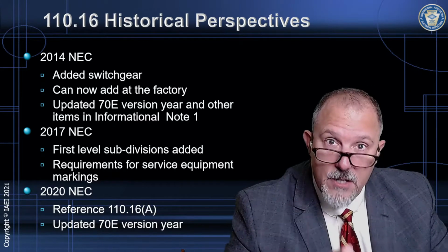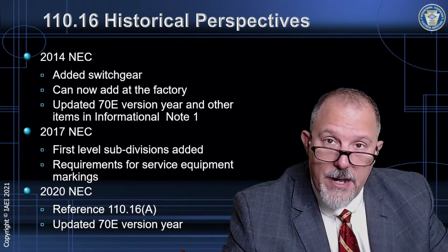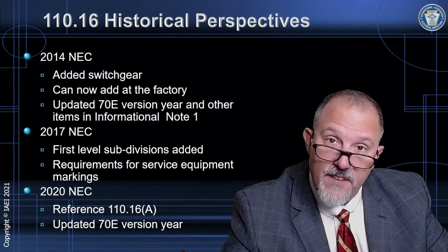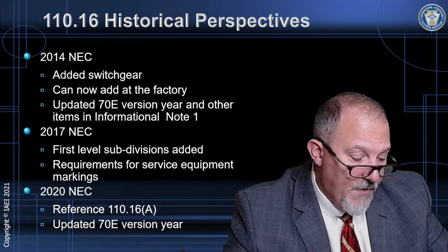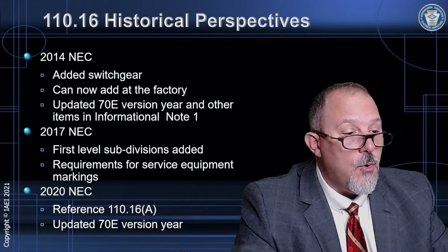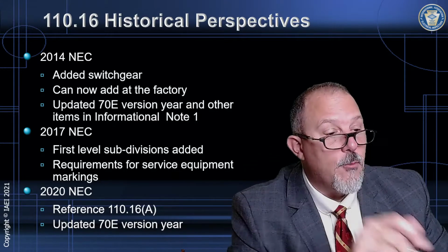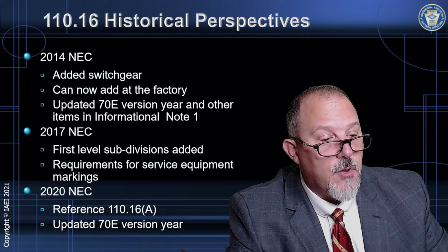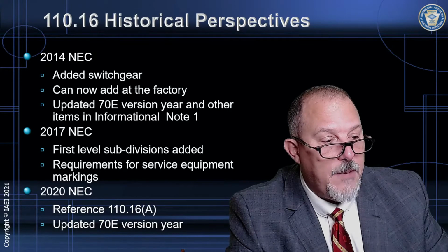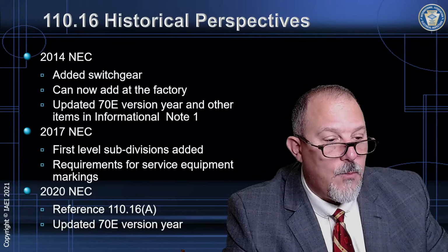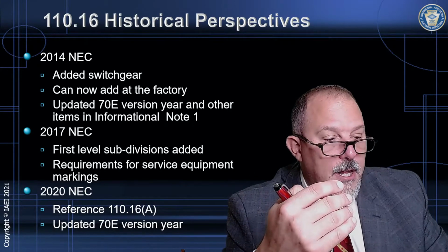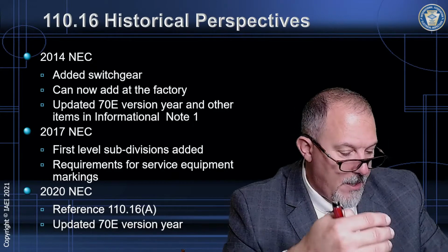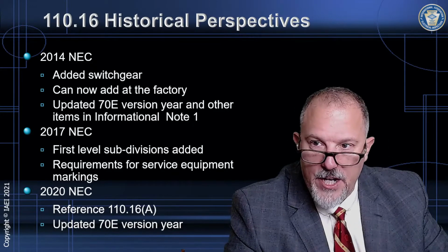If the inspector, the installer, the contractor, the owner, whomever puts on a field marking, a field applied hazard marking, there's a whole set of requirements and references to ANSI Z535, product safety signs and labels. It talks about adequately warning of the hazards, talks about being permanently affixed to the equipment and durable, and all that jazz.